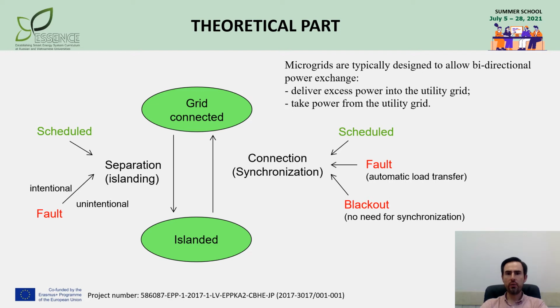Islanded mode can also result from external grid disturbance or loss of utility interface due to a disaster. If the microgrid's own generation is not adequate to supply the load, then part of the load, the non-critical load, will be shed. In such a case, transfer from grid-connected to islanded mode is done automatically by means of protection and a main switch. If island operation is possible and the microgrid can self-balance, such conditions are called intentional islanding. If islanded operation is forbidden but happens, this is called unintentional islanding, which shall be detected and eliminated.